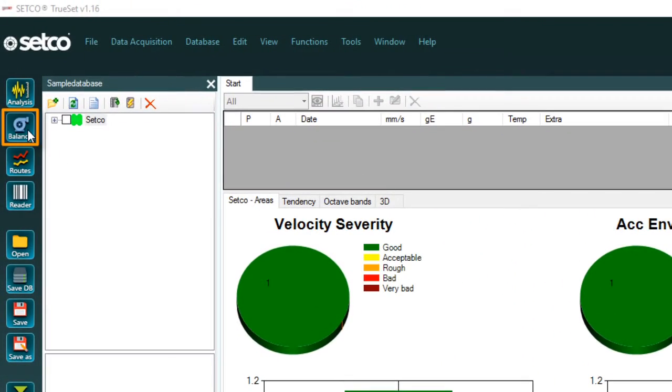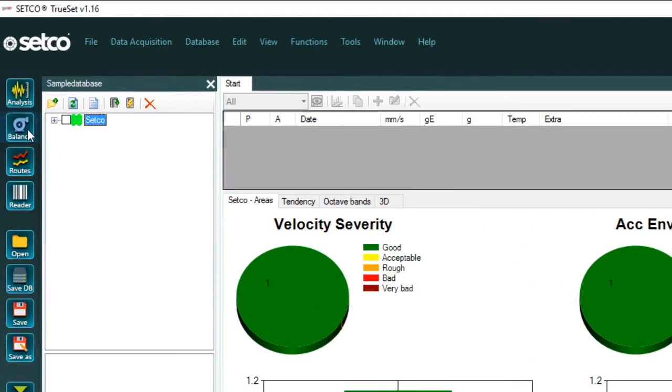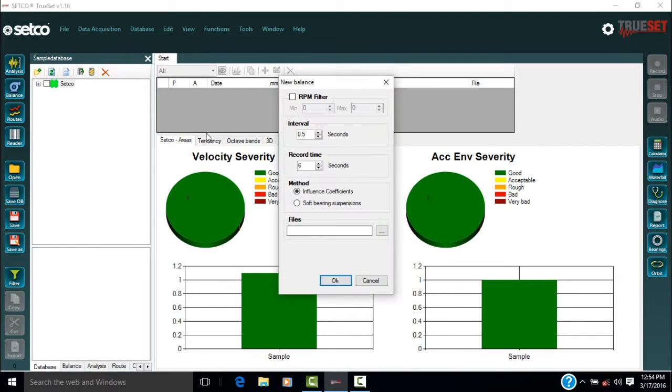To start, click on the balance button on the left side. Now select the RPM filter checkbox. Enter in minimum and maximum values that are 200 to 400 RPM above and below the intended running speed. It is important to record every run at the same RPM. The more consistent the speed, the more accurate the results will be. Now click OK.